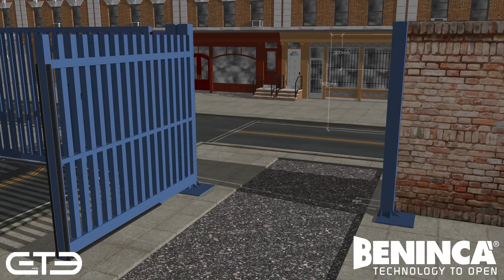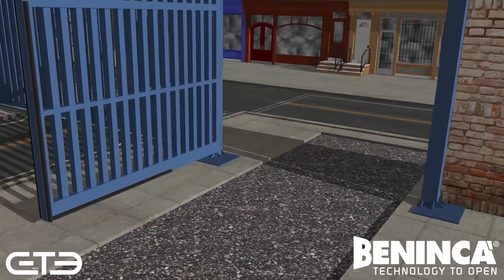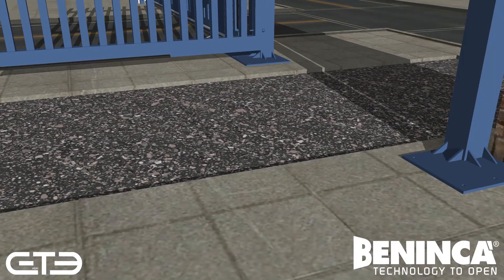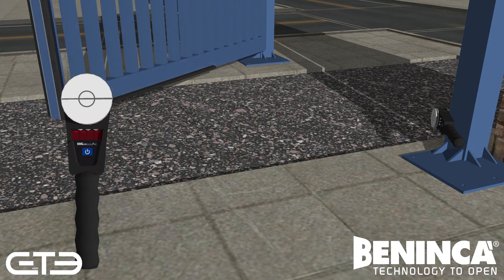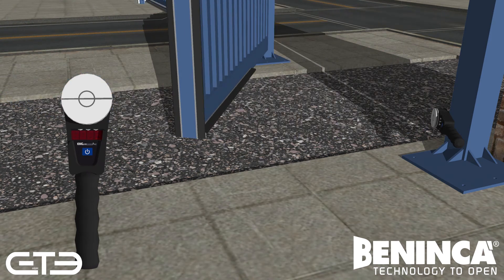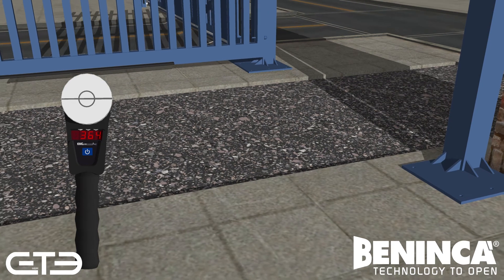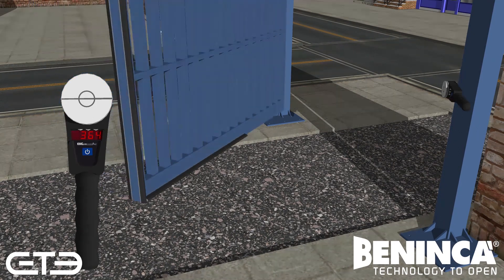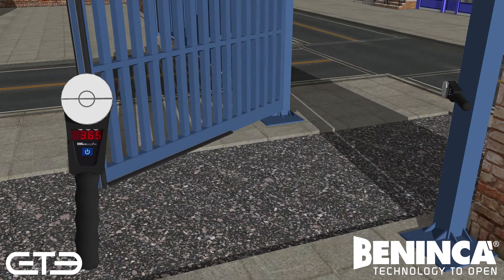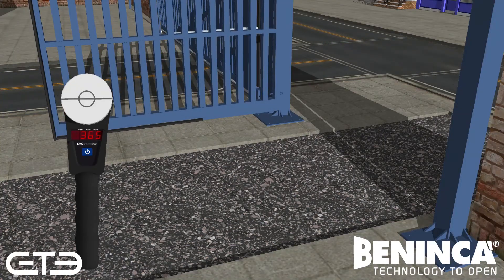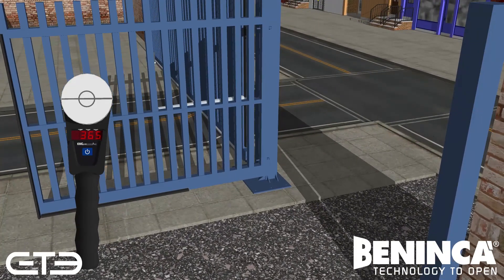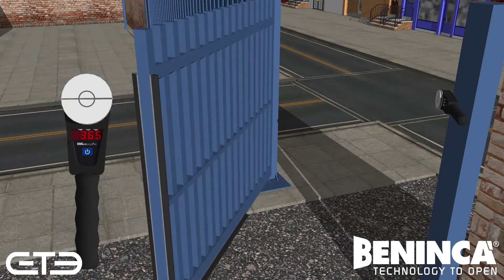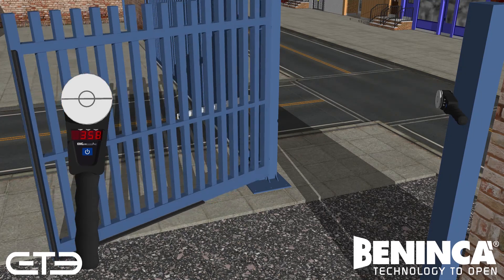Moving on to the swinging gate — these can be a little trickier than the sliding gate, as your measurements must now create an arc following the gate rotation, and the instrument may need to be placed at an angle. To start, place the instrument at 50mm up and 50mm across. Take your readings and record them, then repeat the process two more times. Now place the instrument halfway up and 50mm across and repeat the process. Then again for 300mm down, 50mm across. When all is done, you should have 9 results and 3 averages.